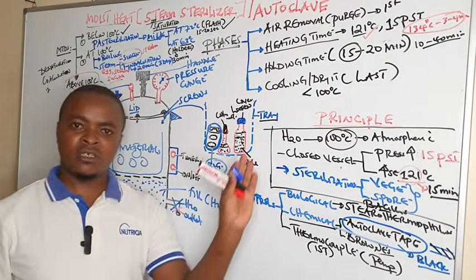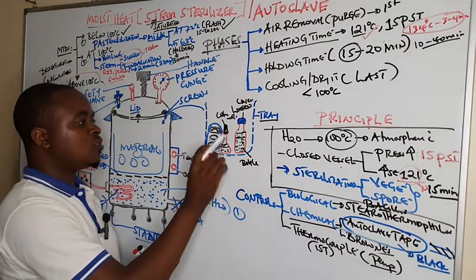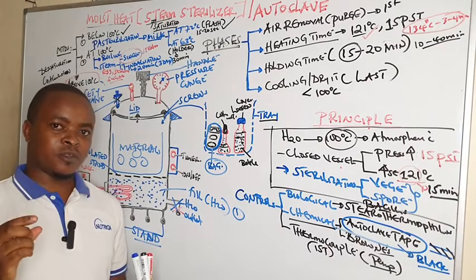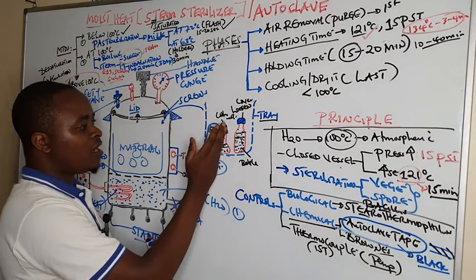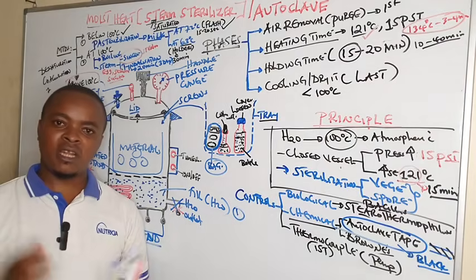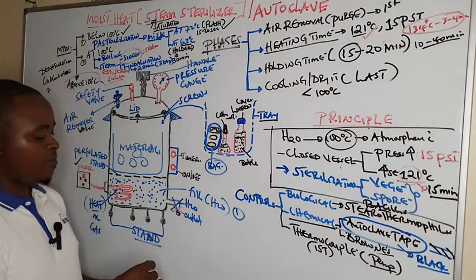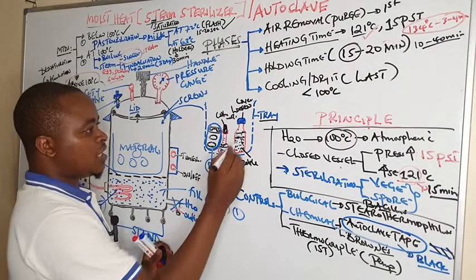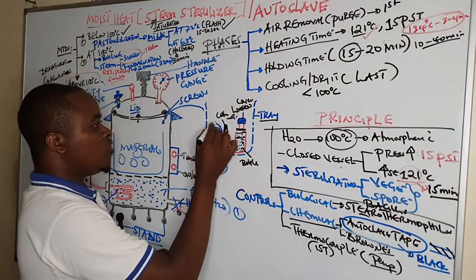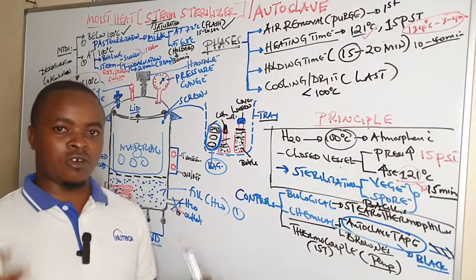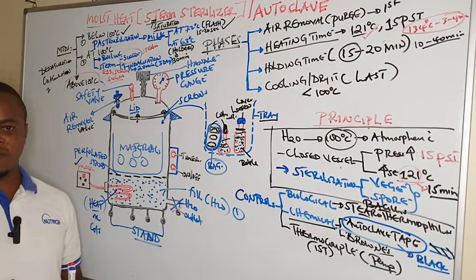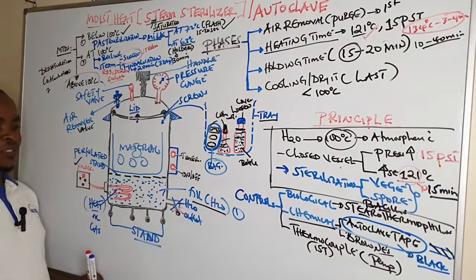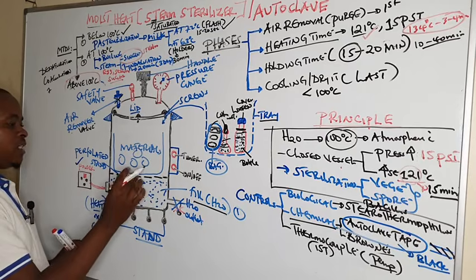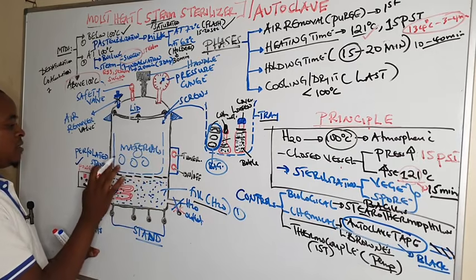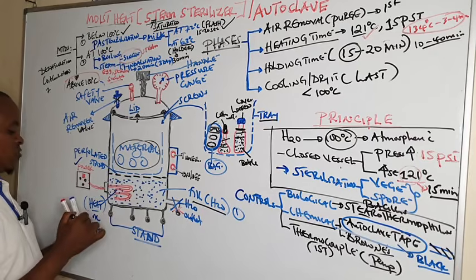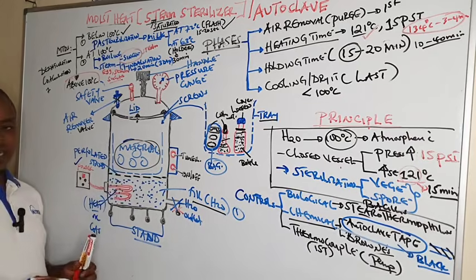While packing the materials, always make sure you leave space in between so that there is free circulation of steam, because we are using saturated steam, so we don't overpack. We must leave spaces in between the autoclaved materials. And after packing them, always remember to add the control, such as the masking tape, the autoclave tape. On each material you put the autoclave tape as a control to see if the maximum sterilization was achieved. So we have filled the tank with water until it covers the heater. Then we load our perforated tray with our materials to be autoclaved, without forgetting to add the control, the autoclave tape.